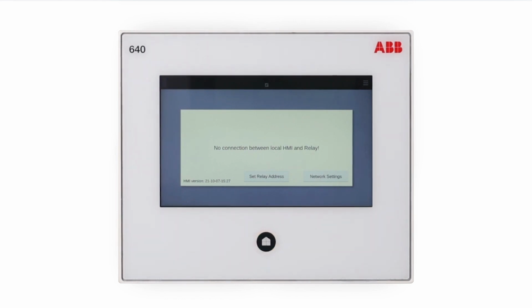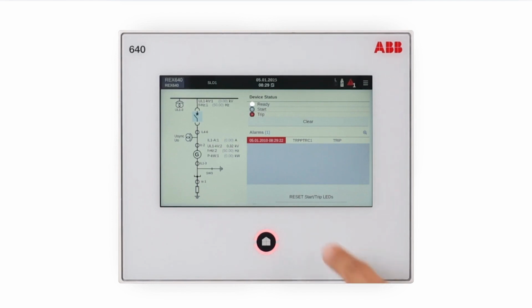Low frequency blinking red indication will indicate that the process related alarm is active, or process related alarm has been active earlier but is not any more active. If the process-related alarm is active, the home button will show steady red indication. In case the relay's IRF is activated, but it communicates with LHMI, the home button shows high-frequency blinking red indication.